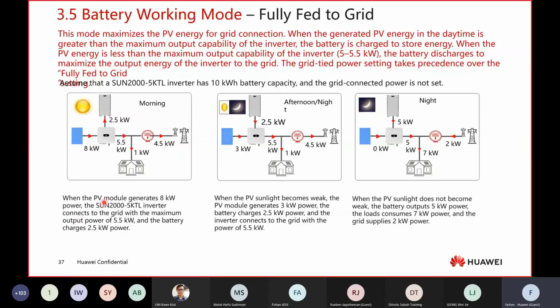Okay, so from here, for example, your PV system can generate 8 kilowatt, right? Then for the 5 KTL, the power output will be up to 5.5 kilowatt. So the system will give you 100% of whatever the inverter can produce, 5.5. Then the remaining PV will start charging the battery. And during that time, your load is 1. So the remaining, 5.5 minus 1, will be sent to the grid. So you get the money here.